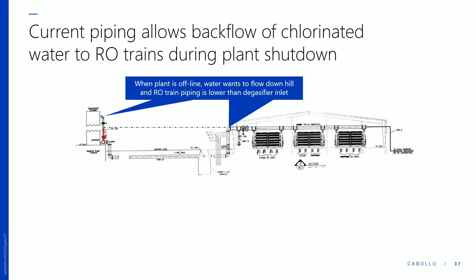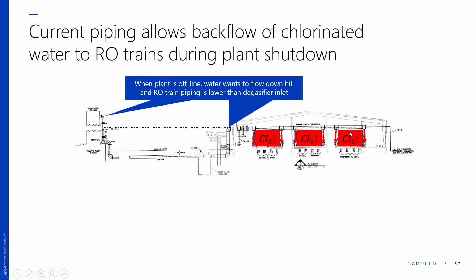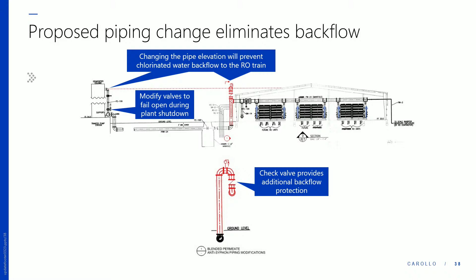So we want to fix that, and one of the projects that we recommended, we talked about last time, was fixing some piping arrangements on the plant. Right now, the degasifier elevation is higher than the RO trains, so when the plant is offline, the water that flows from the RO trains to the degasifiers can actually flow backwards, and it does, and it chlorinates those RO trains. So the piping modification that we'd recommended was changing the elevation of this pipe leaving the building so that it was slightly higher than the degasifiers, and adding a check valve. So this will be one of the projects that you see recommended in the end.